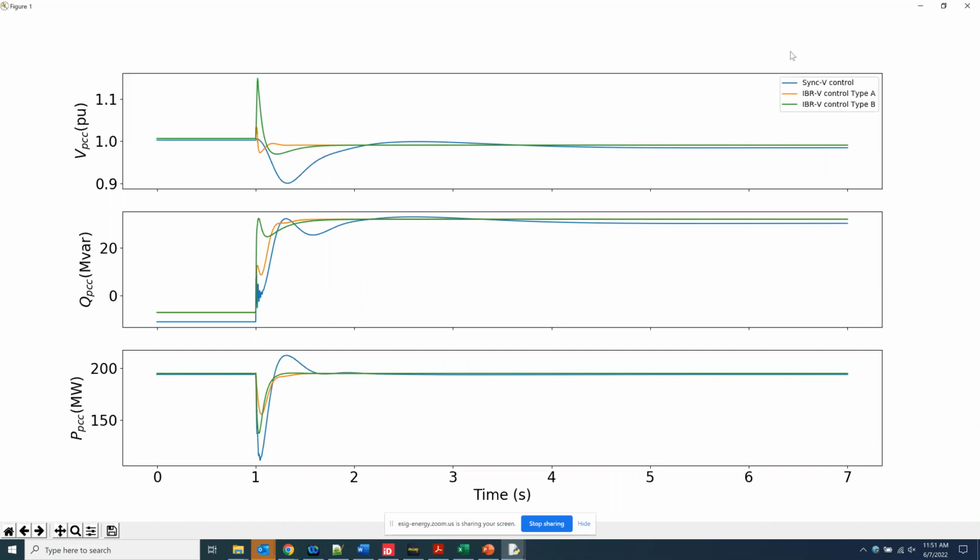These other ones, the window gets bigger in different directions. And as an industry, you're talking about what service you need, so I can translate that into how stable does it need to be? What are you trying to accomplish? You gave an example, having worked with a company that had the inverter you're talking about. There've been examples where those wind plants have tripped onto islands where there was load, they were within the attraction of that system, and they ran for extended periods of time. If that isn't grid forming, what is it?